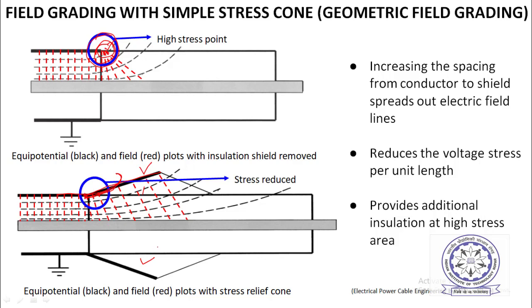What is done is the semi-con layer is extended — either in a straight line or in a curved fashion — using a construction known as a stress cone. This stress cone is external; it is not part of the cable but is laid over the cable whenever termination is required. You can see the equipotential surfaces have been pulled a little farther away.